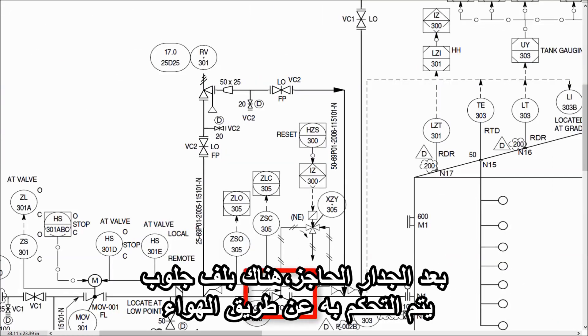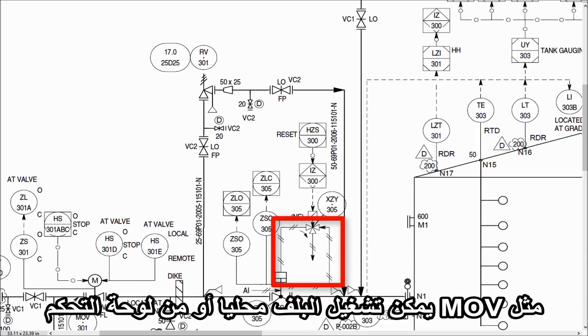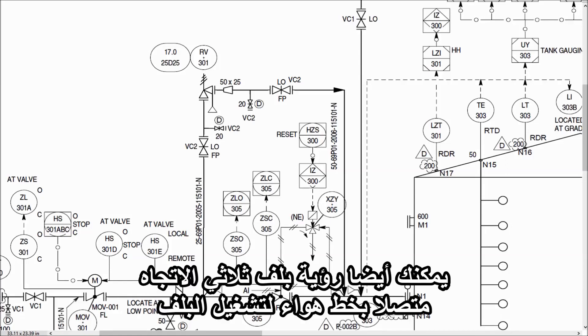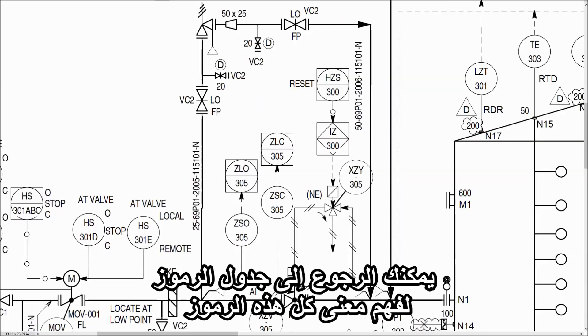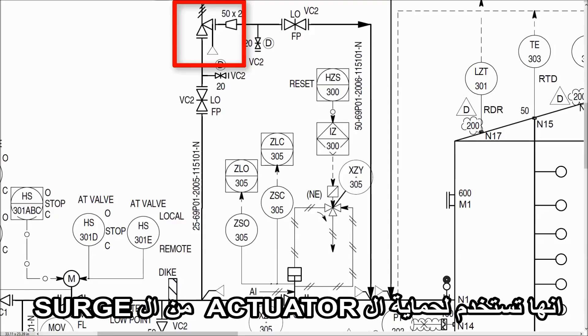After the dike valve, there is a pneumatically controlled globe valve. You can see the pneumatic line symbol. Like MOV, the pneumatic valve also has various switches to operate the valve locally and from the control panel. You can also see the three-way valve connected to the pneumatic line to operate the actuator. You can refer to the abbreviation table to understand the meaning of all these instrument bubbles. You can see that there is a relief valve in bypass, which is used to protect the actuator from surge.